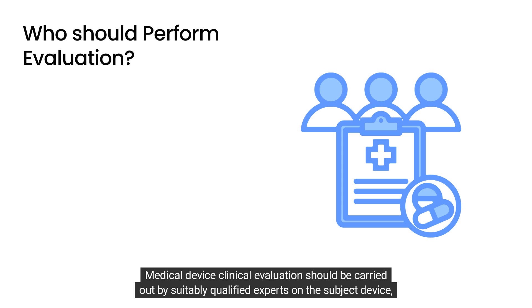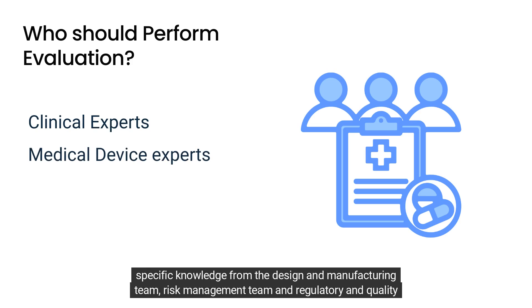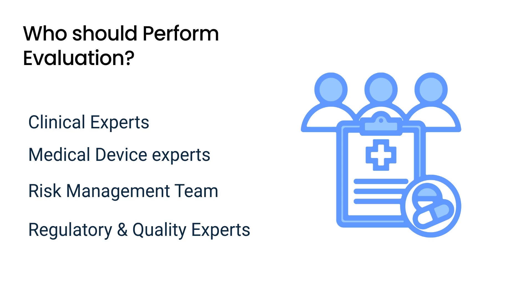Medical device clinical evaluation should be carried out by suitably qualified experts on the subject device. This usually consists of a multidisciplinary team of experts with clinical knowledge, medical device specific knowledge from the design and manufacturing team, risk management team, and regulatory and quality experts.